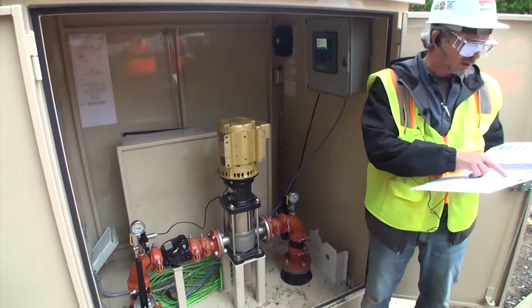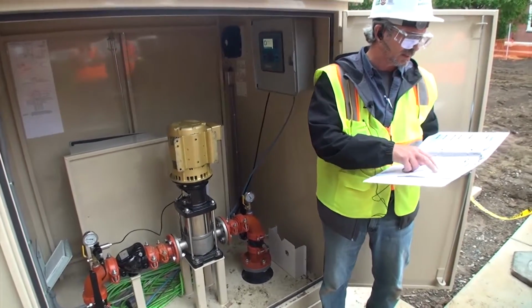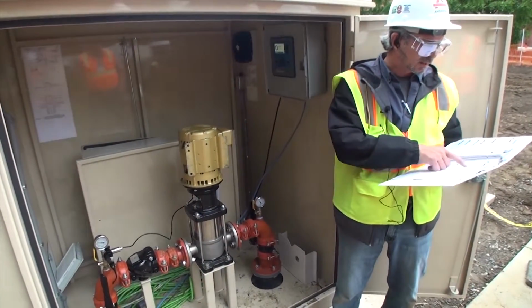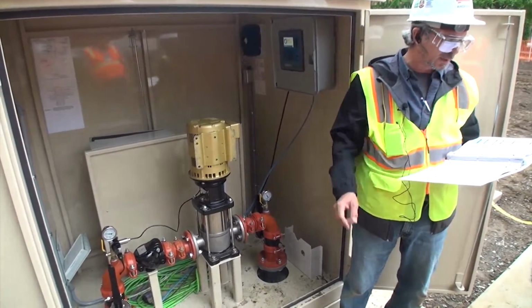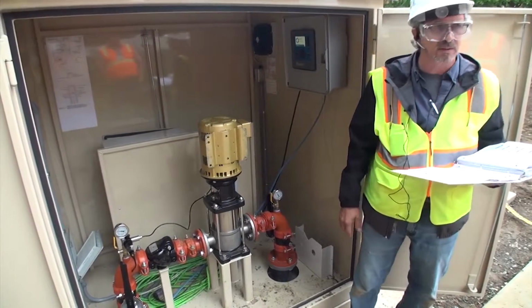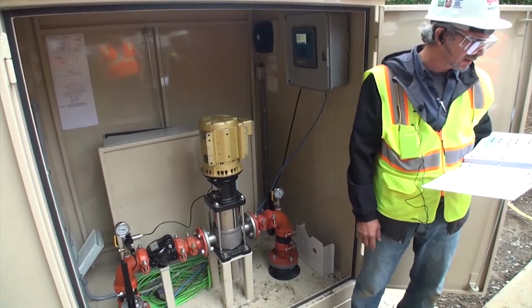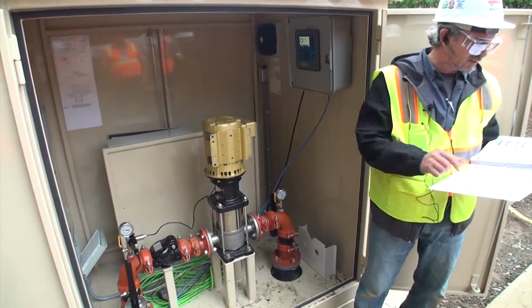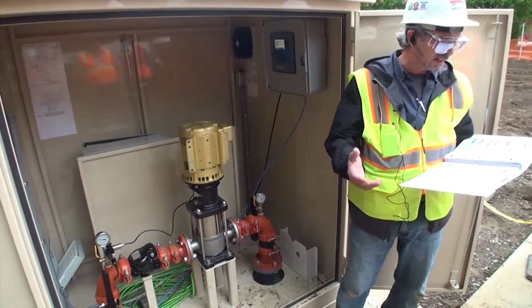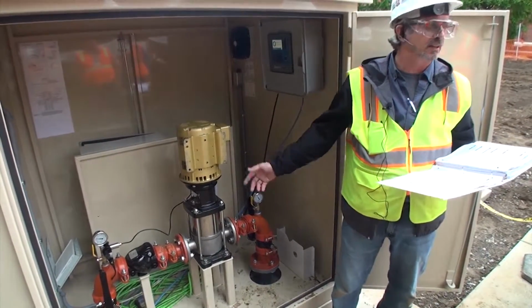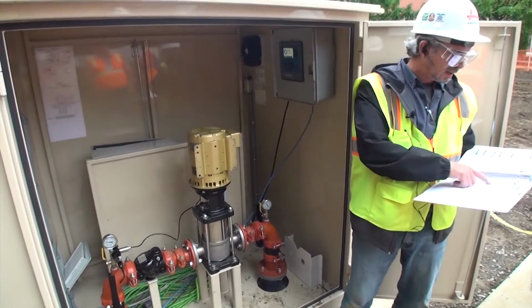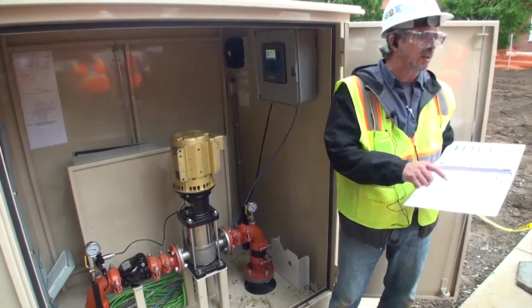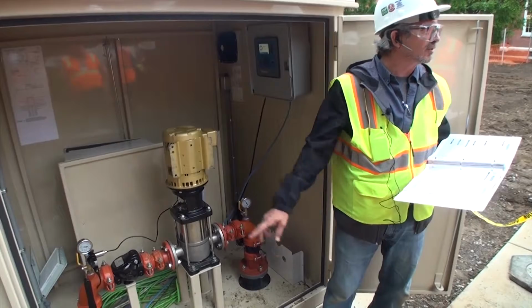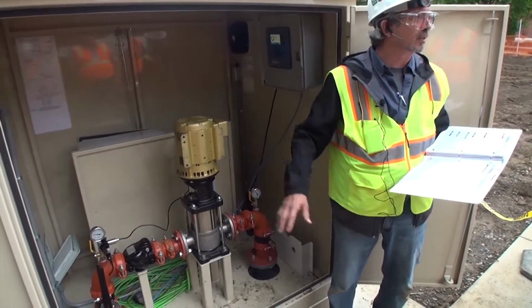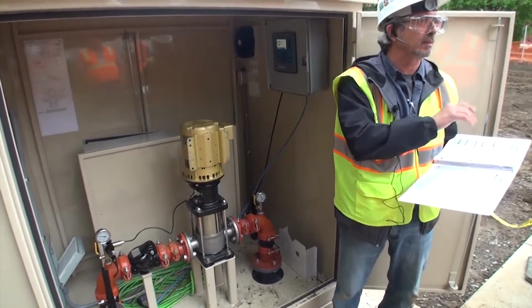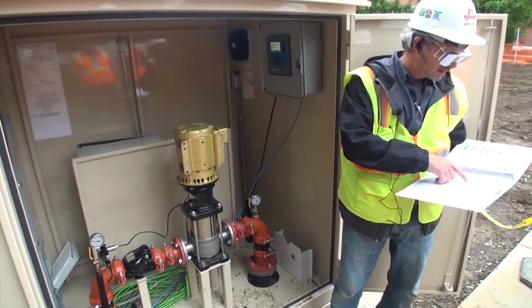So we talked about closing the discharge valve, blowing out the system downstream of the pump. Remove all the drain plugs from the piping and the pump. Do not reinstall the plugs. Set them aside someplace where you can find them again. Drain the suction. Turn off the water from incoming pressure. Disconnect all monitoring devices. Those are the gauges we just talked about. It talks about removing a 1/4-inch line from the transducer. Some stations we build, the transducer is not mounted directly to the pipe, and there's a 1/4-inch line that feeds to it. It doesn't pertain to this station.